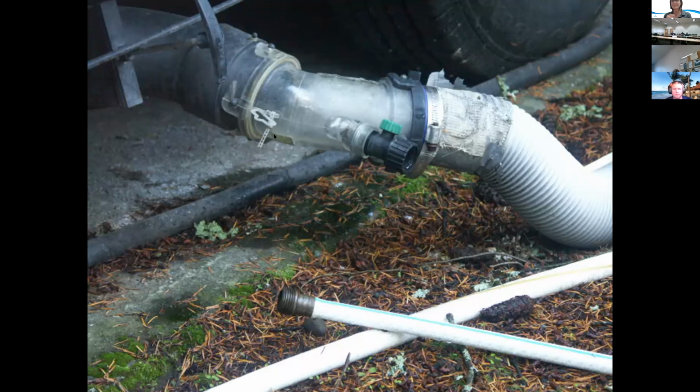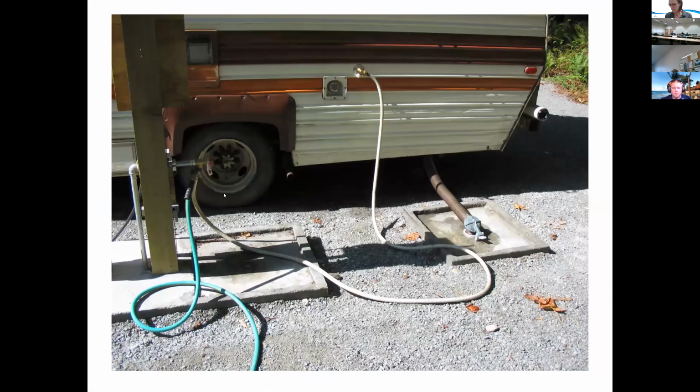There needs to be an RPBA on the dump station. Usually as you're leaving the park, you'll see a little waste dump station. The potable water line there needs to have an RPBA installed. That's a rule. But yeah, these hose bibs everywhere should at least have an AVB, or should have a hose bib vacuum breaker, even though that's not adequate, because as we all know, it can't be under pressure for more than 12 hours in a 24-hour period. Shouldn't have any elevated piping, no downstream valves. You check all the boxes here, but there should be something at RV sites.